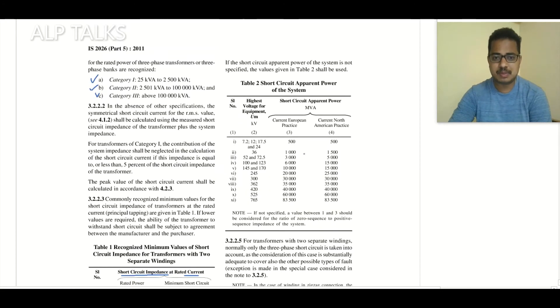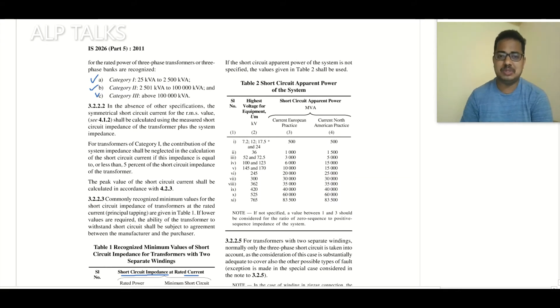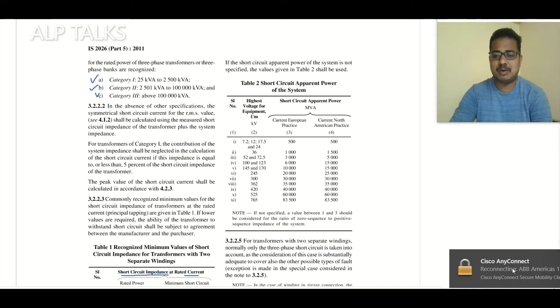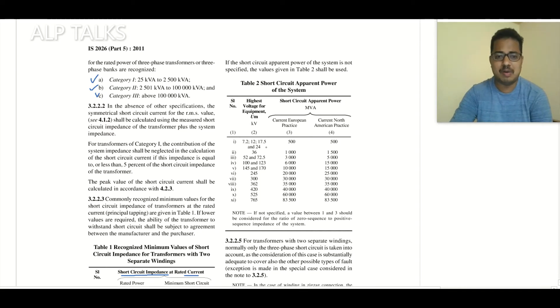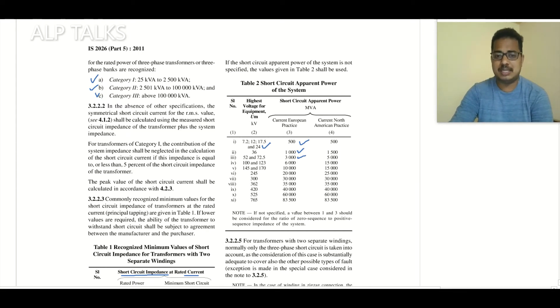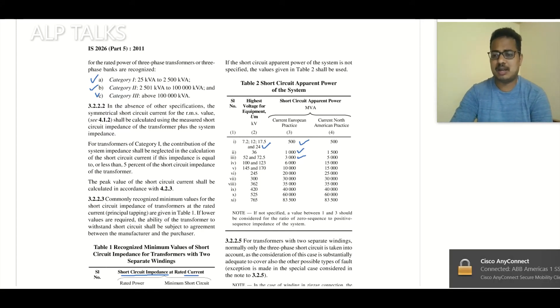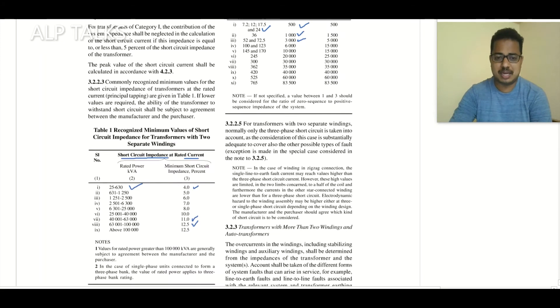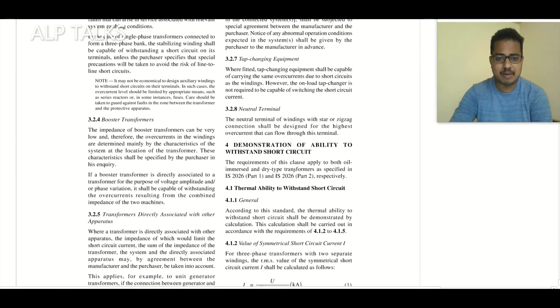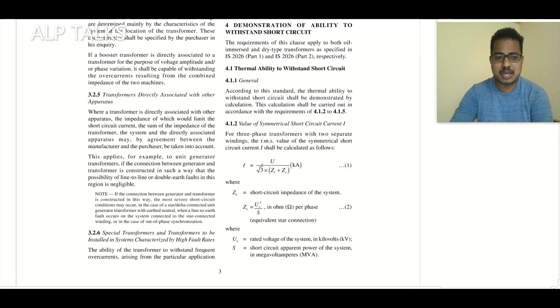You also have short circuit apparent power. If the customer is not specifying anything, you can consider short circuit apparent power as per this table — for example, up to 24 kV you have 500 MVA as per European practice, for 36 kV it is 1000 MVA, and for 52 and 72.5 kV it is 3000 MVA.